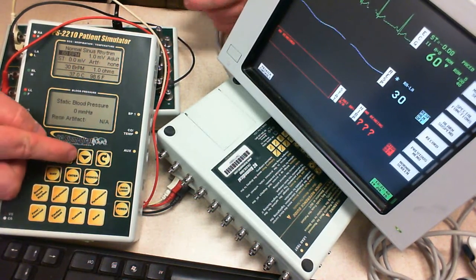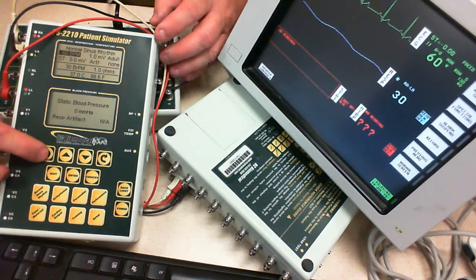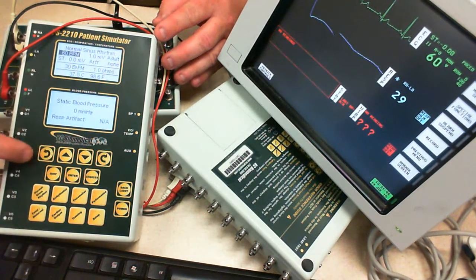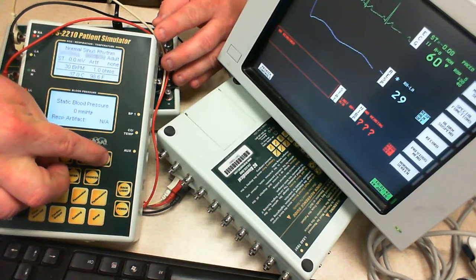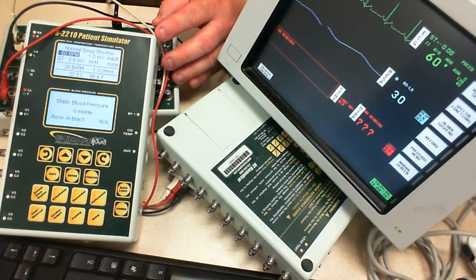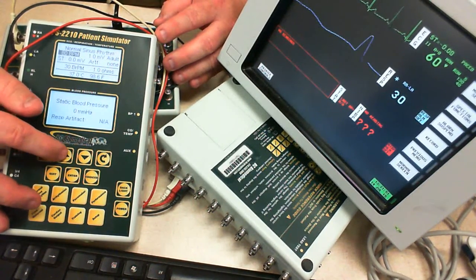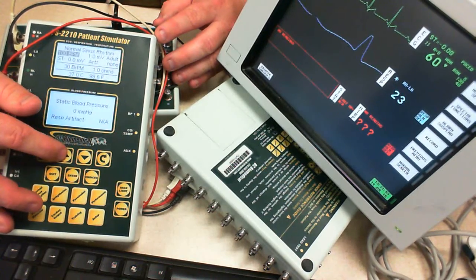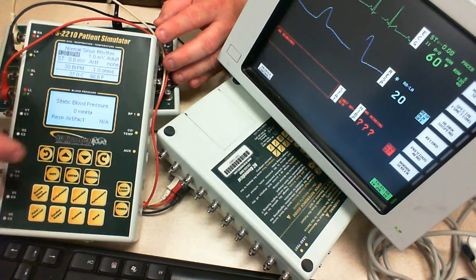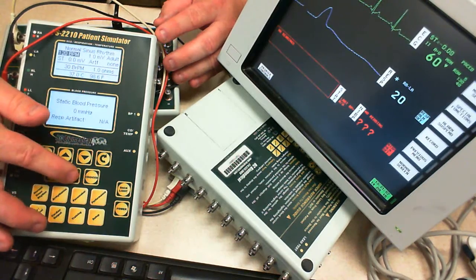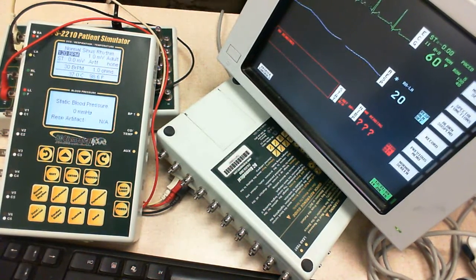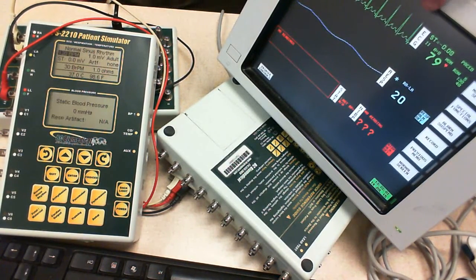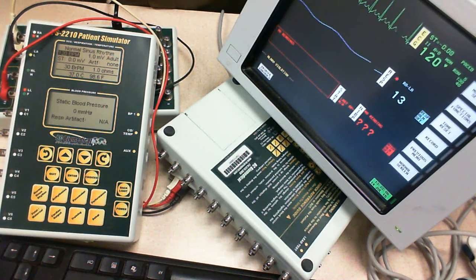What I want to do here is change the 60 beats a minute. So I'm going to hit the up and down arrows. By the way, you select different numbers by hitting the circular measurements, and then you go up by hitting the up arrow. That's 120. I'm going to hit enter. Always hit enter after every change. Notice now we're at 120 beats a minute. And it's violated the alarm, which is an interesting one. We'll go back to that alarm.